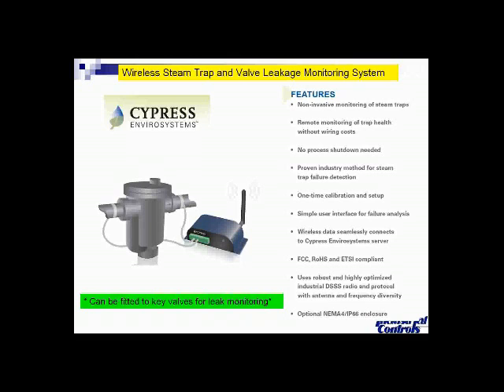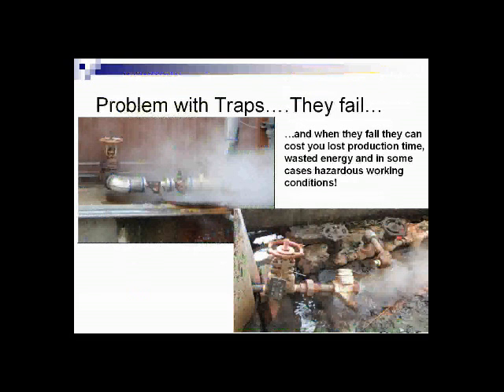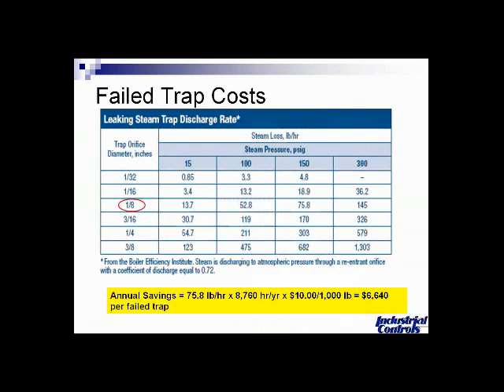Now, again, with steam traps or anything like that, this next slide here will show you that there's a lot of energy loss with steam traps and any valve that's handling steam, because you go to so much effort and energy and cost to heat up the water to steam. When these steam traps fail open, there's a lot of energy loss very, very quickly through those. Not to mention the hazardous working conditions. The failed trap cost could be quite high. In this case, a single steam trap failed open would be about $6,640 of energy costs lost per steam trap.